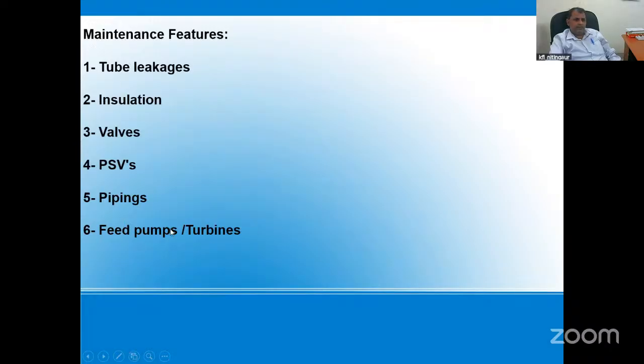These are some equipments where you need to focus on. Tube leakage. To avoid the tube leakage, periodic inspection is necessary. Inspection means to check the thickness, to check any spots on the tubes. If you have any doubt, you can do the DP test, dye penetrant test, because some of the cracks, some of the pinholes are not visible.